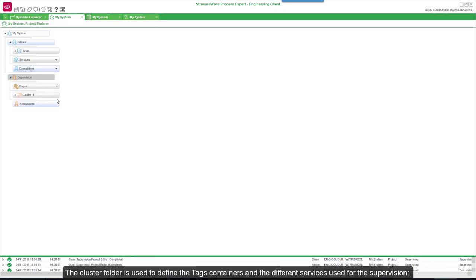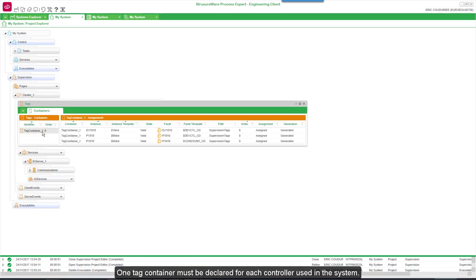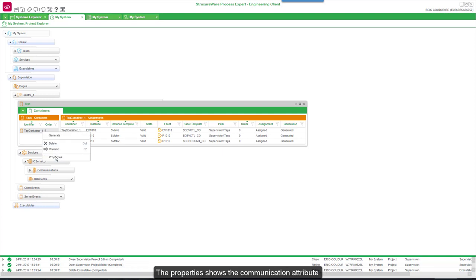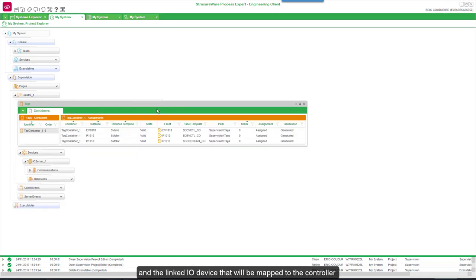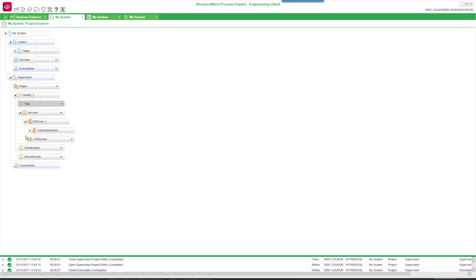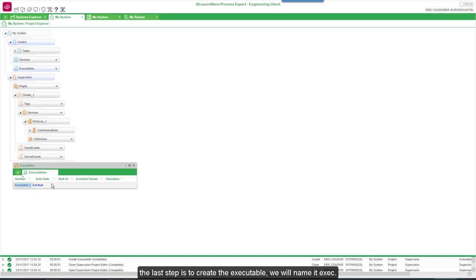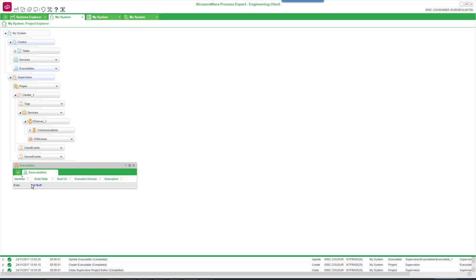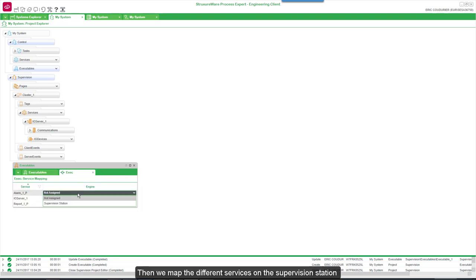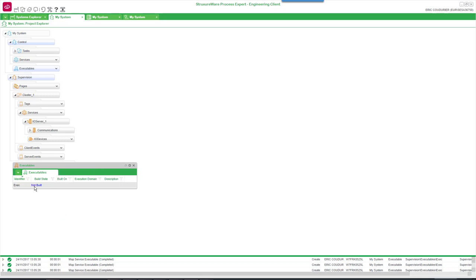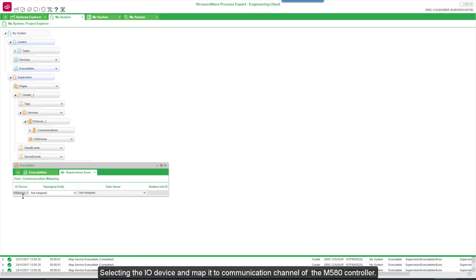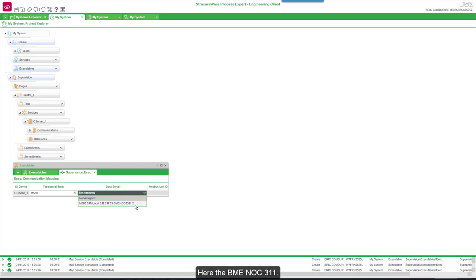The Cluster folder is used to define the tag containers and the different services used for the supervision. One tag container must be declared for each controller used in the system. The properties show the communication attributes and the linked I/O device that will be mapped to the controller. The last step is to create the executable — we will name it exec. Then we map the different services on the supervision station, and finally map the communication by selecting the I/O device and mapping it to the communication channel of the M580 controller, the BME NOC0311.